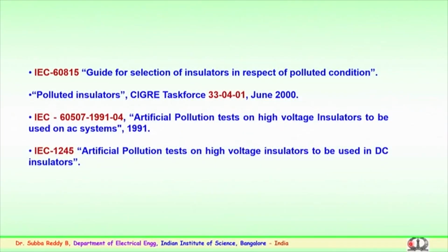I would like to share some information which is in the standards. We have IEC standard 60815. This is a very important guideline which gives the information on the selection of insulators, particularly in respect of polluted conditions. This gives the idea of how the creepage length has to be chosen and how the insulator dimensions have to be chosen depending upon the area where the insulators are being used. There is also a task force by CIGRE 3304 which has come up with an important document on polluted insulators, where it gives the information on how to use insulators, be they ceramic, glass or porcelain, in various conditions.